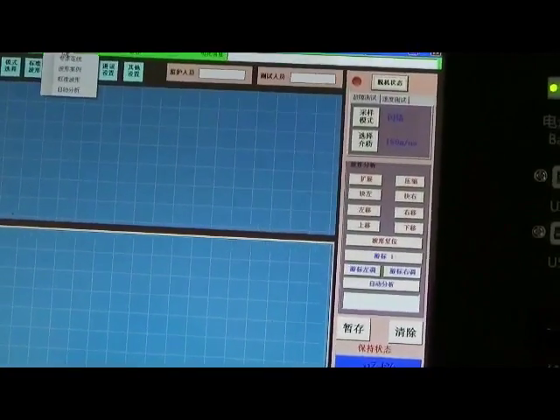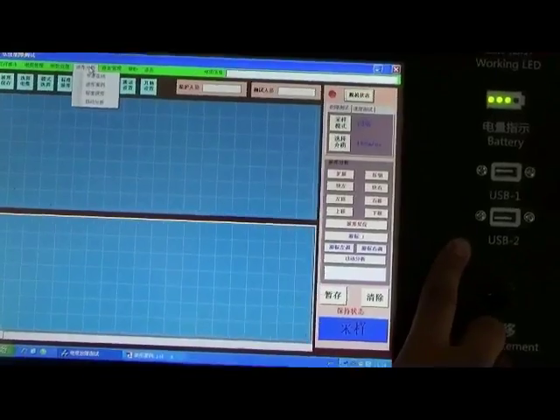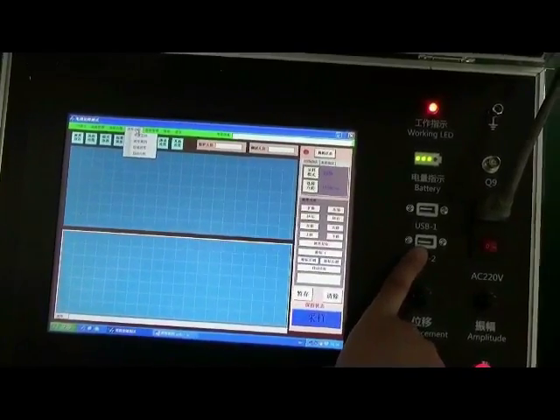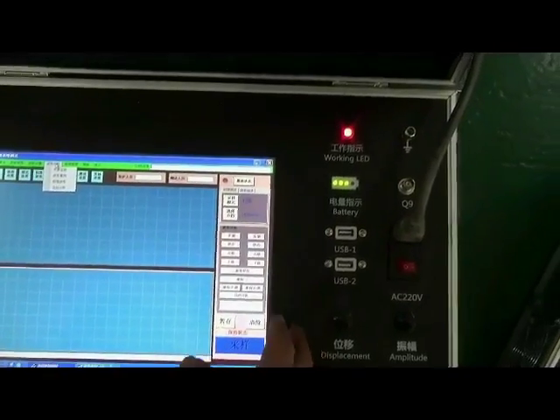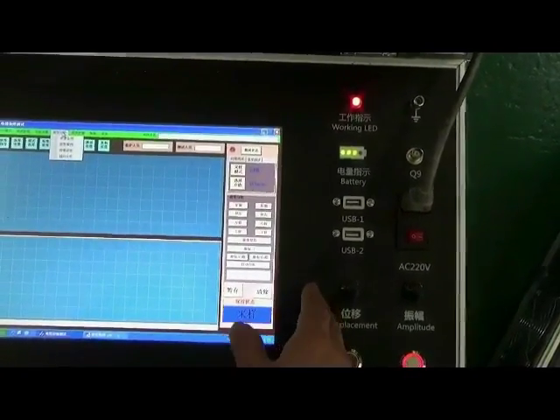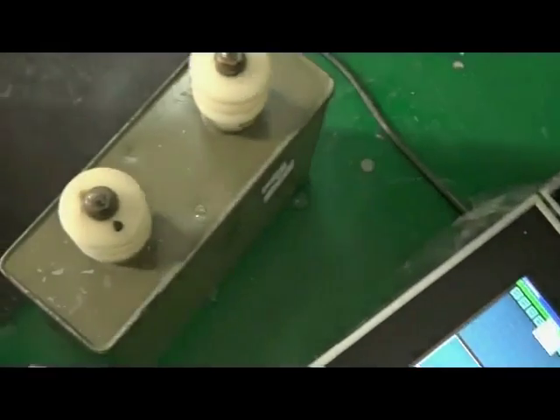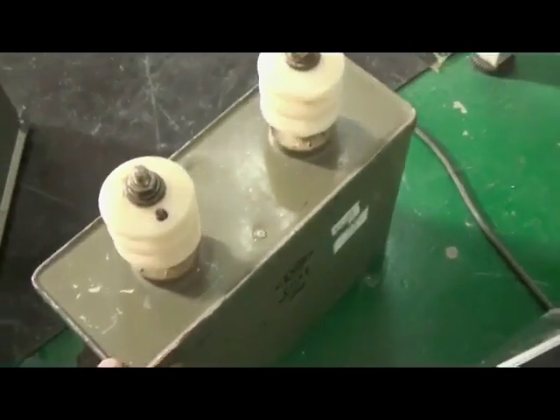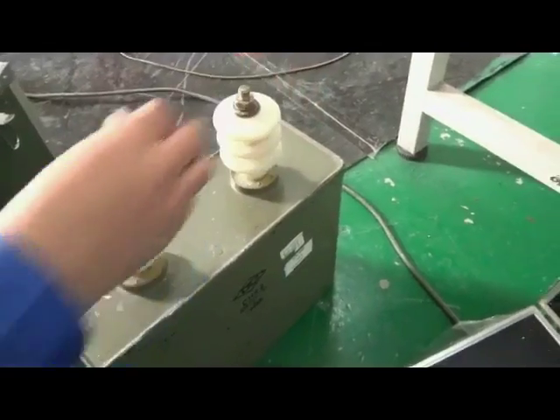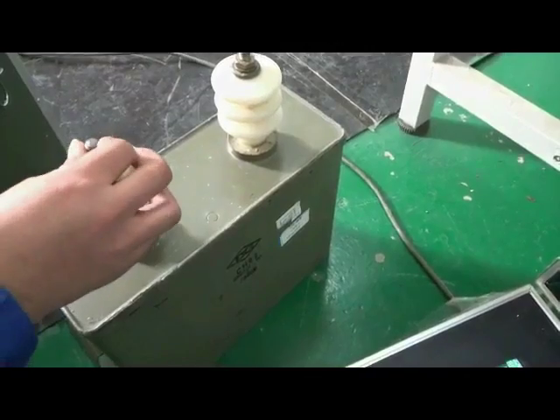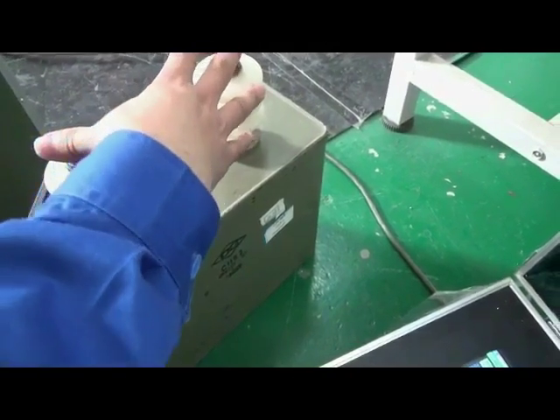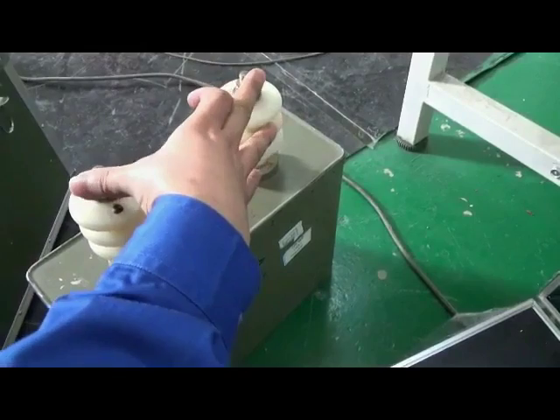High voltage impulse capacitor: make sure routing is correct. Connect discharge route well and fully discharge. It must be connected by short circuit wire if it doesn't work for a long time to make sure there is no stored voltage.